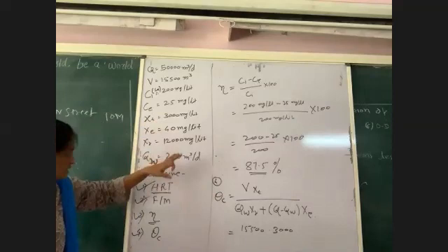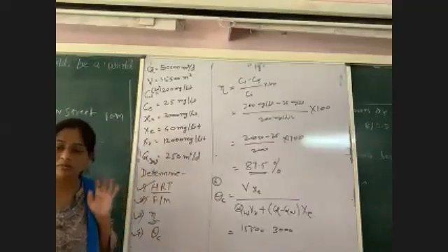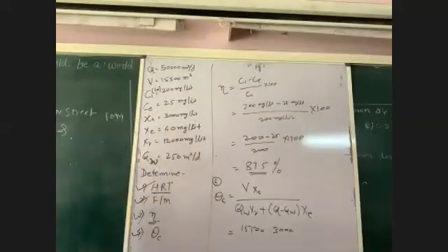Sometimes the F by M is not given. That time also you should assume from that chart. Okay, usually only these two parameters may ask you to assume. So you should remember these. F by M ratio for conventional 0.3 to 0.4, and for complete mix it is 0.5 to 0.3, and MLSS concentration for the conventional type of aeration tank it is 1500 to 3000 milligram per liter, and for the complete mix it is in the range of 3000 to 4000.